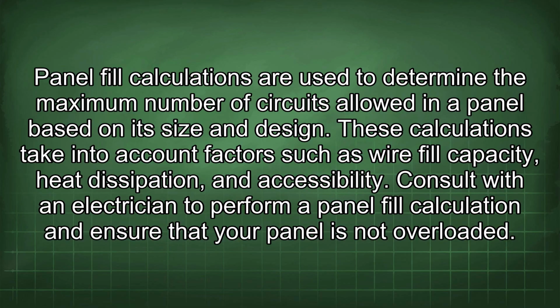Panel fill calculations are used to determine the maximum number of circuits allowed in a panel based on its size and design. These calculations take into account factors such as wire fill capacity, heat dissipation, and accessibility. Consult with an electrician to perform a panel fill calculation and ensure that your panel is not overloaded.